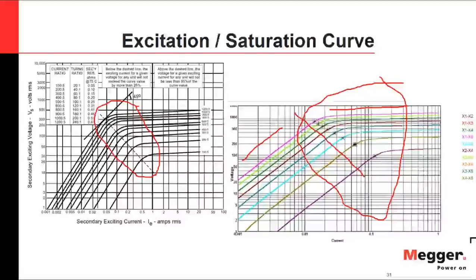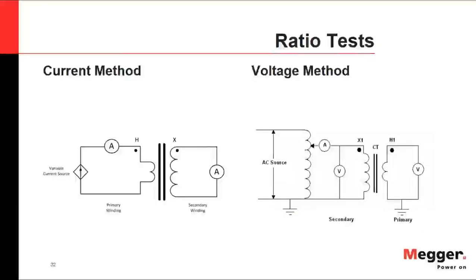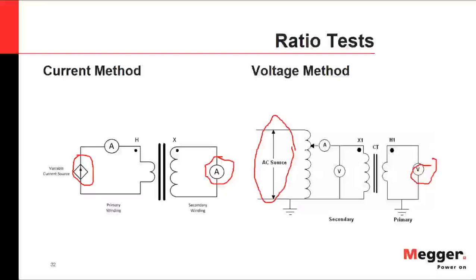For the current method, you need a variable AC current source, which may require sourcing currents up to 1000 A or 2000 A on the primary side — a significant practical challenge. An ammeter on the secondary measures the reflected current. The voltage method is simpler: you apply a sinusoidal AC voltage and measure voltage on the primary side. Since the CT secondary is low voltage, this can be done with voltages that in most cases do not exceed 300 V AC, allowing use of a small, lightweight test unit in the field.